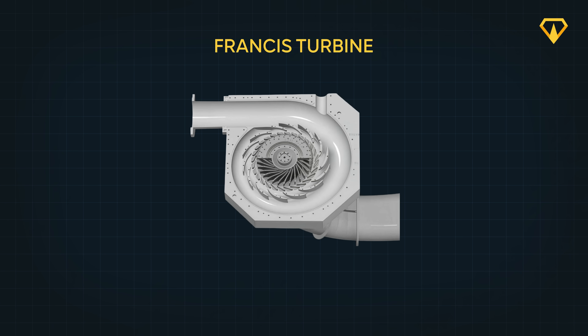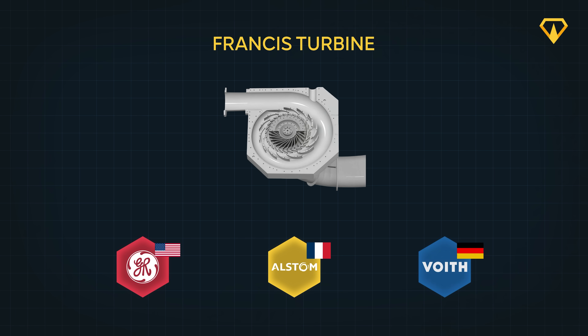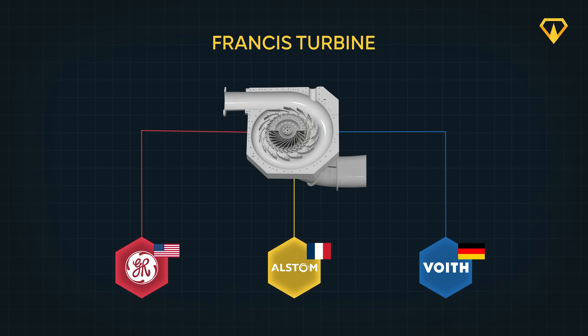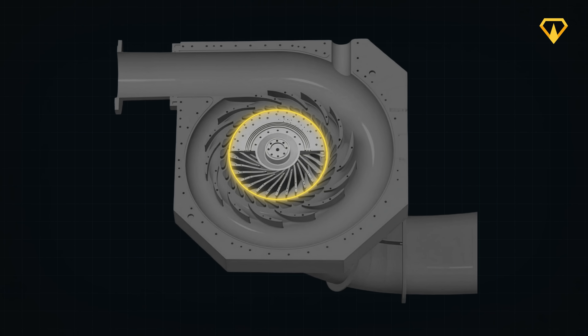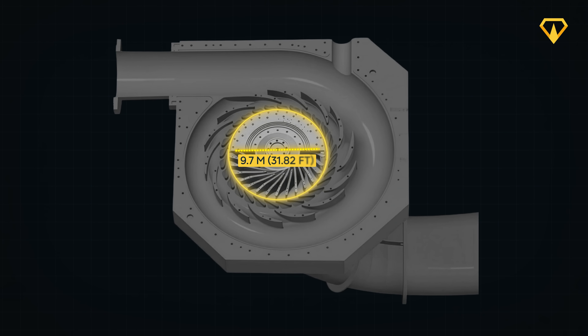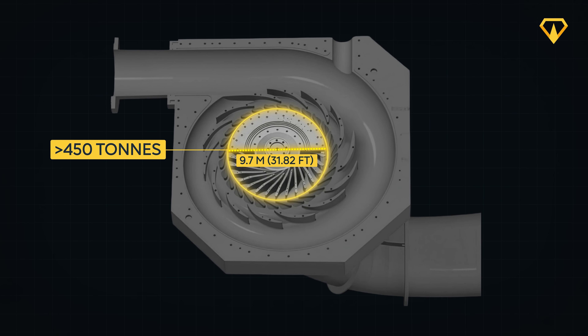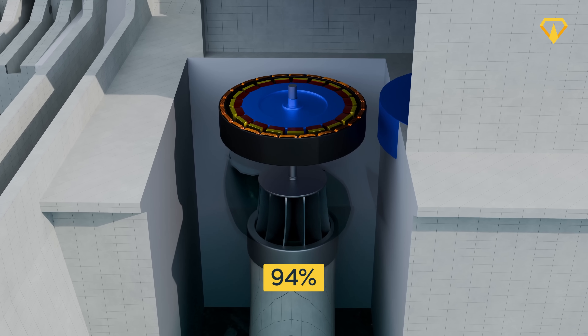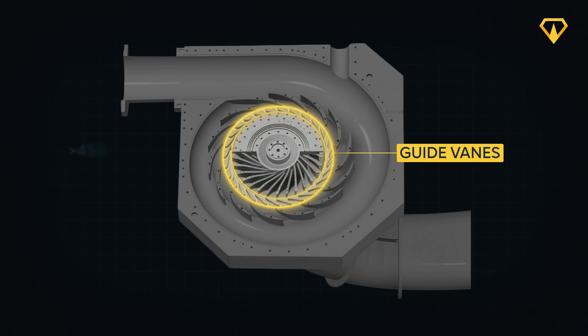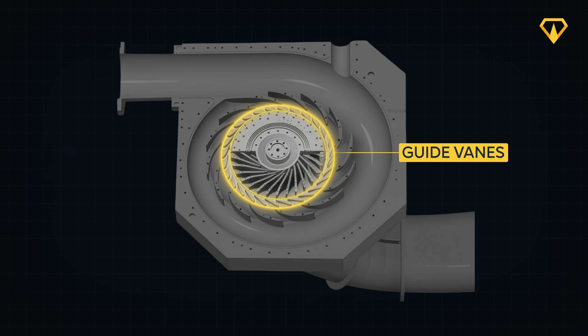To build them, the Chinese government brought together an international dream team of engineering heavyweights — including Alstom from France, GE from the US, and Voith from Germany. Together, this team redesigned many essential components of the turbines, starting with the runners: the main wheels with curved blades that make the turbines turn. They made them 9.7 meters in diameter, weighing more than 450 tons each. They also designed them to be extremely efficient, able to convert 94% of the water entering the turbine into electricity. The guide vanes that direct water flow into the turbines were also built specifically to handle the extreme pressure of the Three Gorges Dam.